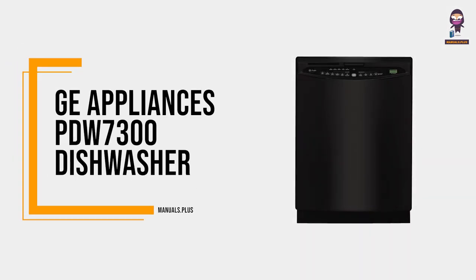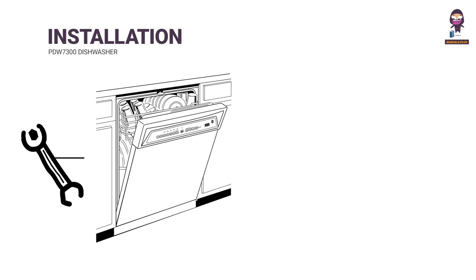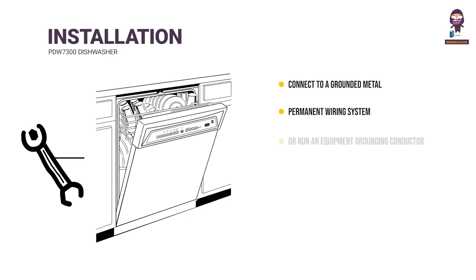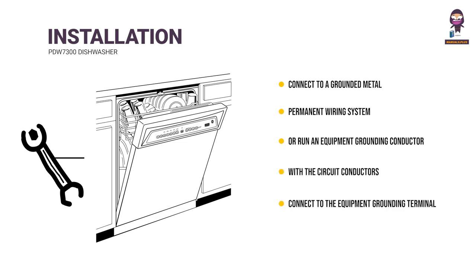Introducing GE PDW7300 Dishwasher. Proper installation. Connect to a grounded metal, permanent wiring system, or run an equipment grounding conductor with the circuit conductors and connect to the equipment grounding terminal or lead of the appliance. Use supply conductors rated at least 75 degrees Celsius.